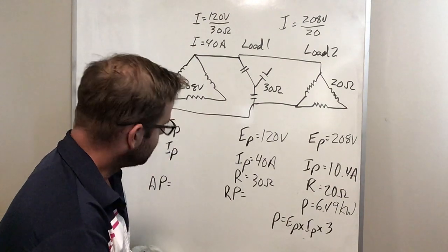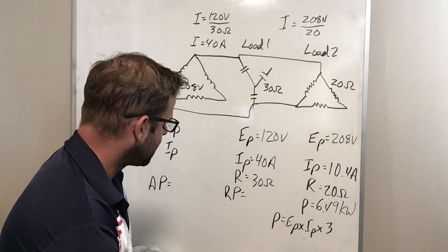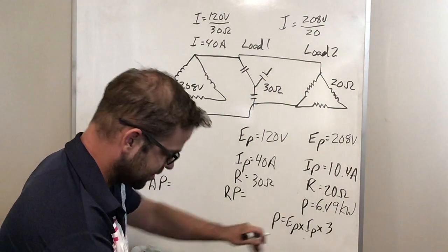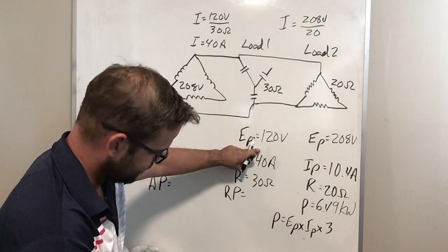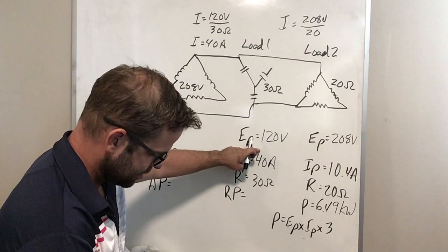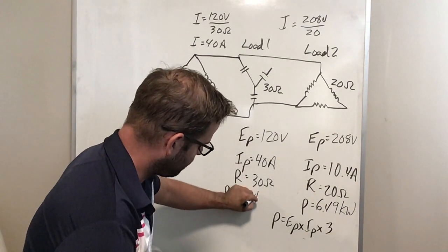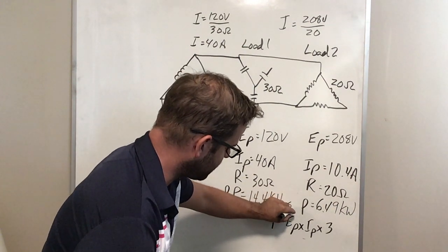Our reactive power, our VARs for our capacitive load, we're going to do the same thing, but we're going to do 120 volts times 40 times 3. We get an answer of 14.4 kVARs.